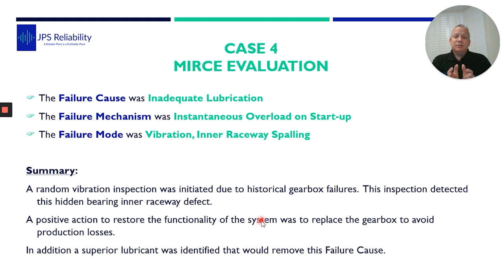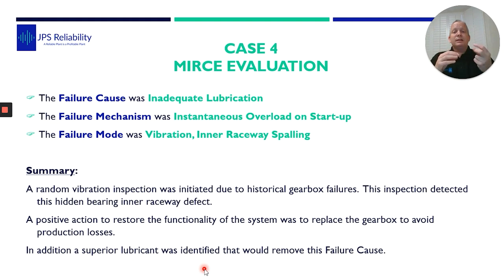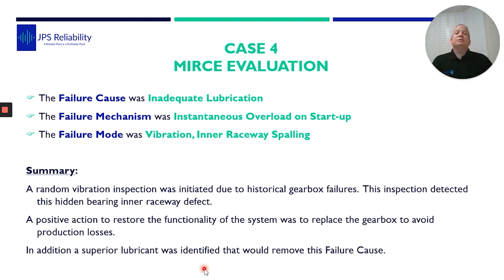Positive action was taken to restore system functionality — a controlled changeout was performed before failure. The system could still produce for the customer without affecting the business. In addition, we suggested using a superior lubricant with additives that cause the oil to stick to the bearing when the gearbox stops, reducing the probability of instantaneous overload damage on startup. At some sites this particular oil has eliminated the inner race defect issue on this specific gearbox model.